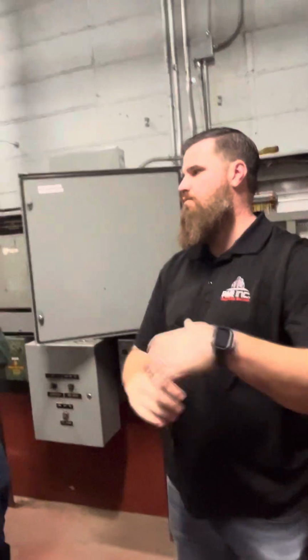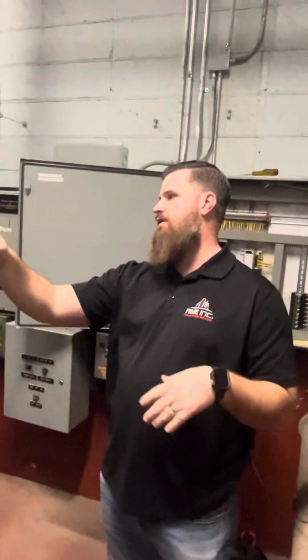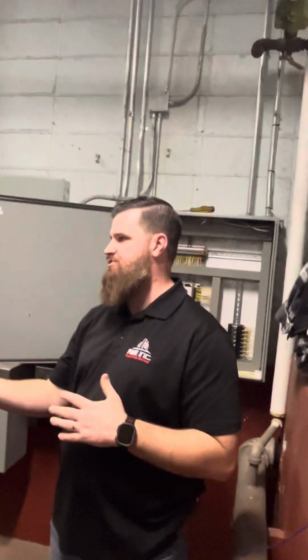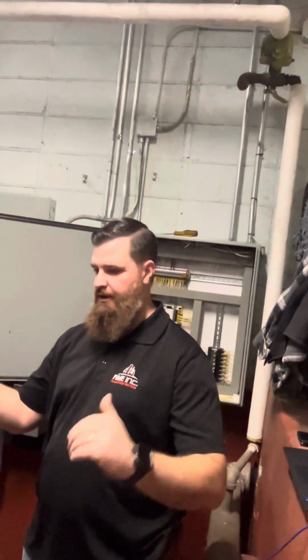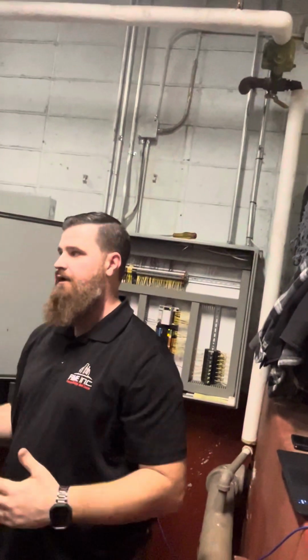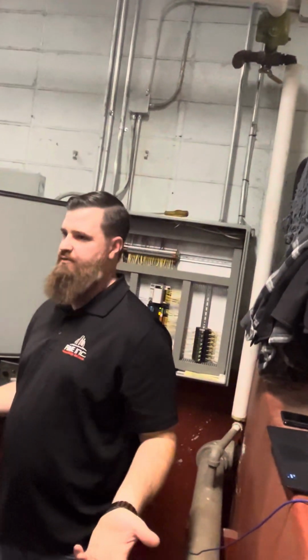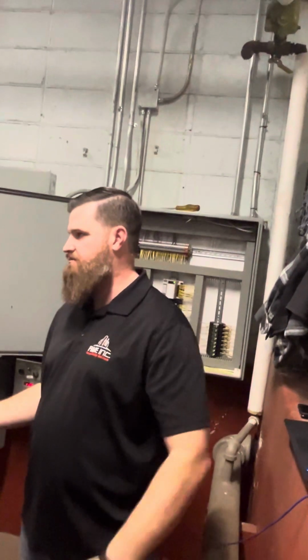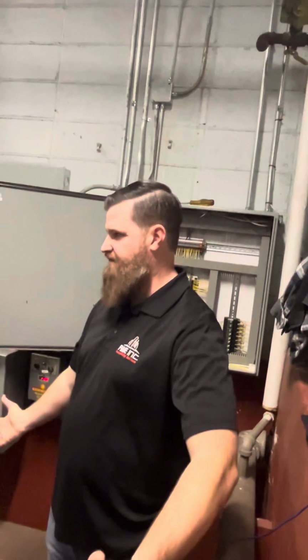Got it. So we also have to make sure his set point on the boilers is set high enough that we can allow this all to operate, because as he approaches set point, he starts to throttle it back. That may cause us to inadvertently fire an additional boiler to get up the pressure. But if all his boilers are set for 3 pounds and I'm trying to get to 3, I need to be above 3 to turn off, or I'm never going to turn off. We're just going to be running 3 boilers at 3 pounds at low fire, which is a waste of energy.